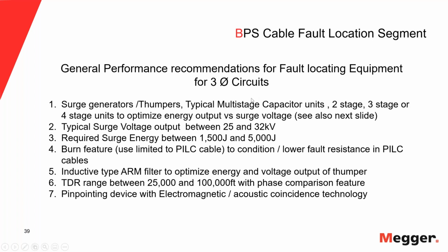Some people are concerned. They say, "Oh, so much current." Well, let's put this all in perspective. A good burner has maybe 500 milliamps, maybe 1 amp. We make some burners that can do up to 20 amps. But if you really look at it, that current is nothing compared to the normal operating current on these cables, okay?